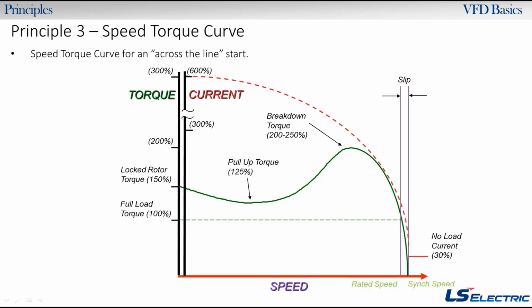Now, an important thing to see here is there's rated speed and then there's synchronous speed. So synchronous speed is 60 hertz, 1800 RPM. So if you had a 4-pole synchronous motor, the electrical field in that motor is going to be rotating at 1800 RPM. But most of these motors are not synchronous motors. They're just standard induction motors, and they'll have a rated speed of 1750, 1725, something like that. So if you look at a nameplate, that's what you're going to see. So you're going to be more at rated speed.